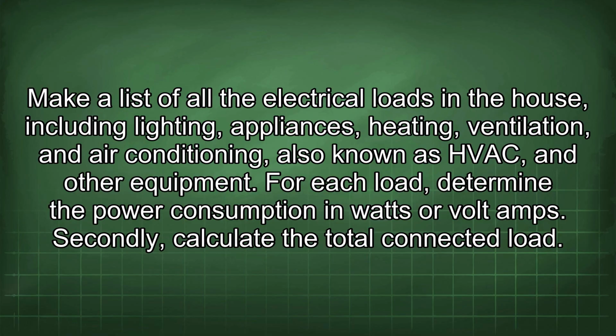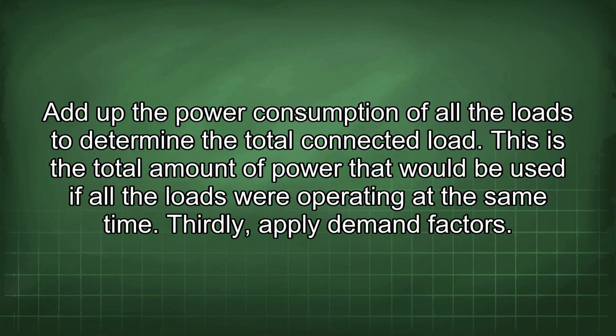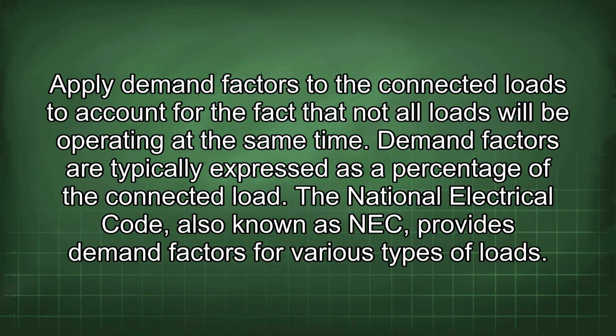Secondly, calculate the total connected load. Add up the power consumption of all the loads to determine the total connected load. This is the total amount of power that would be used if all the loads were operating at the same time. Thirdly, apply demand factors. Apply demand factors to the connected loads to account for the fact that not all loads will be operating at the same time. Demand factors are typically expressed as a percentage of the connected load. The National Electrical Code, also known as NEC, provides demand factors for various types of loads.